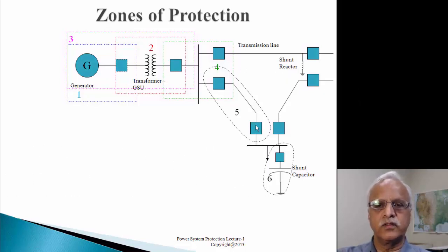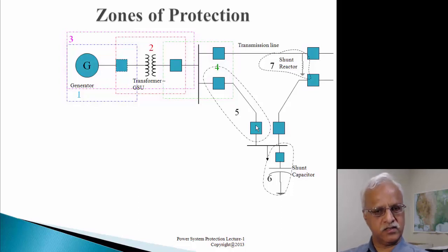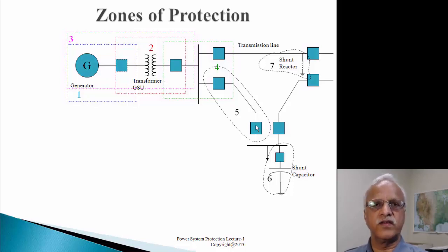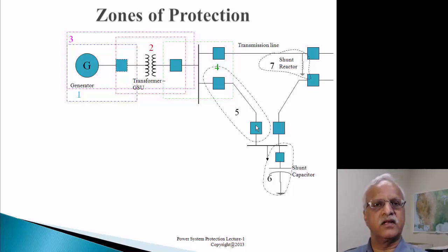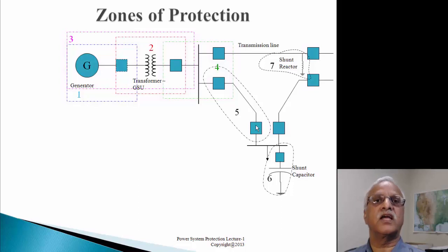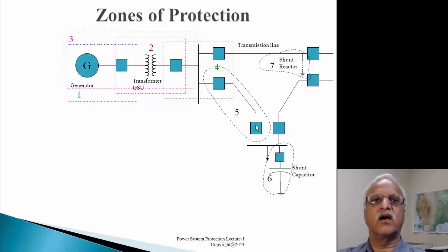We also have two reactive power devices: a shunt capacitor and a shunt reactor. Under heavy loaded conditions, voltage may fall outside the normal operating range, so we need reactive power to boost it back up. Under light load conditions with all transmission lines connected, there is a tendency for voltage to be higher than the normal acceptable range. Under such conditions, we put shunt reactors to pull the voltage down within normal operating limits.